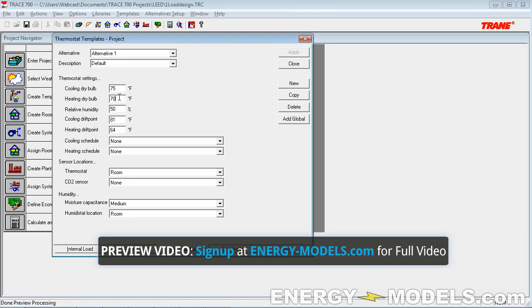The other thing to mention — and I see this on a number of files that we review — people forget to switch the heating dry bulb and cooling dry bulb to be within five degrees. They need to be five degrees apart; that's a rule by LEED. So the heating dry bulb cannot be 72 degrees or we're violating that rule. It's something that, because of the defaults in TRACE, people sometimes forget.